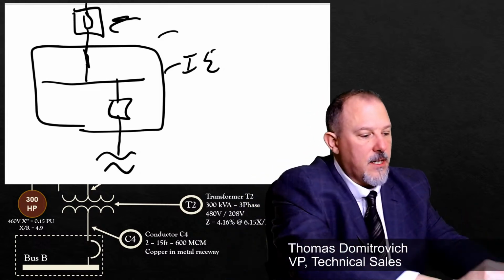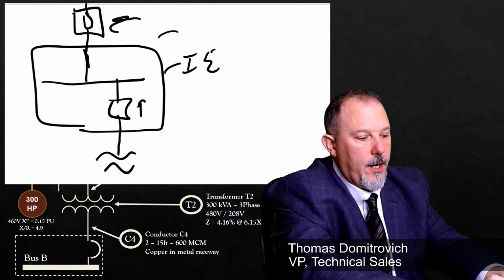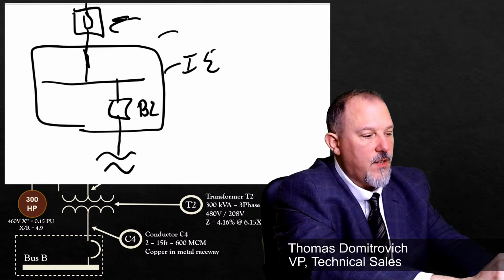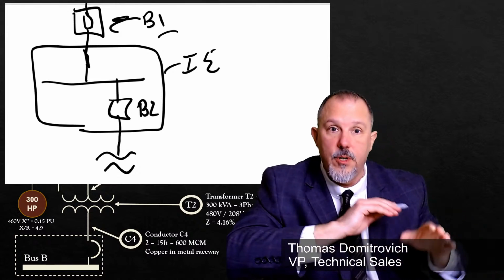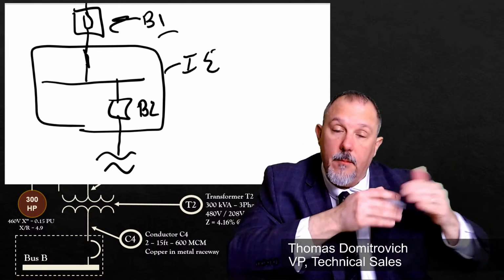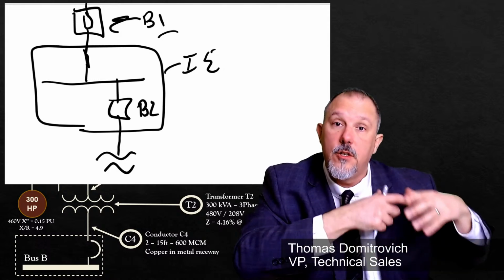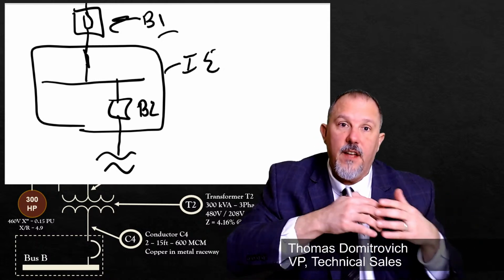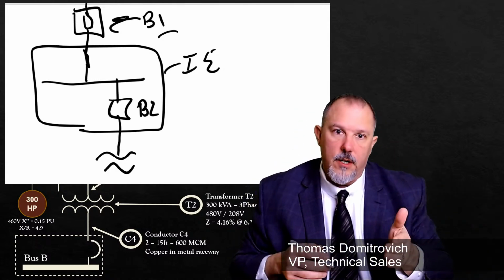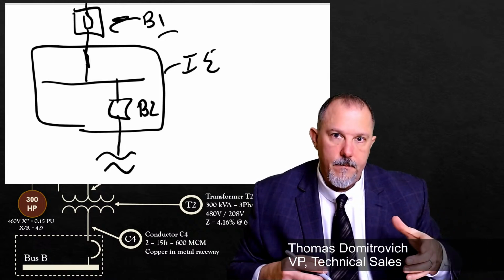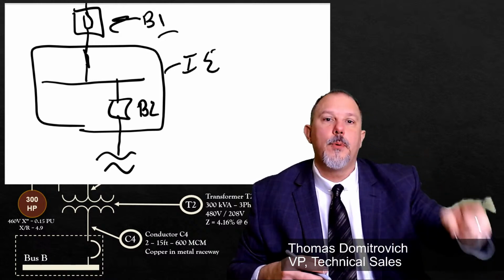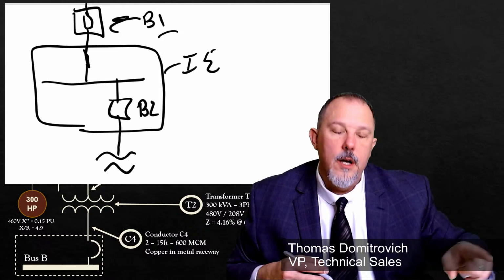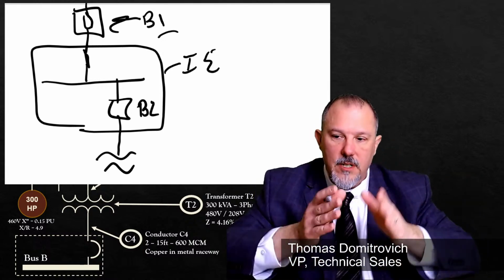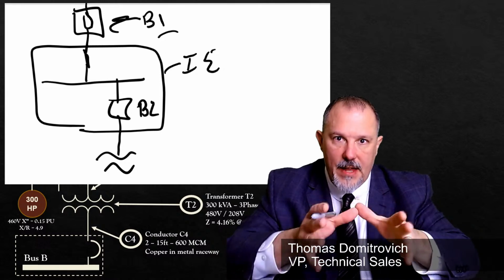But if I need to selectively coordinate breaker 2, which is the feeder going to that transformer, and breaker 1, which is the main, or would have been the main, but just feeding that 2000 amp switchboard, if I need to make sure that the fault current that both of these see is less than the instantaneous pickup of breaker 1, the incident energy, that tells me for sure I'm either in the short time delay band of that trip curve, which, remember, what's a short time delay?